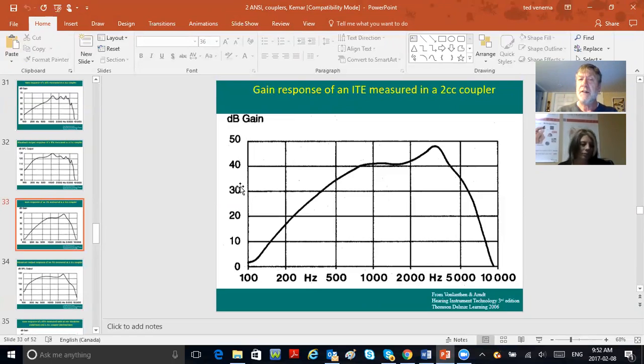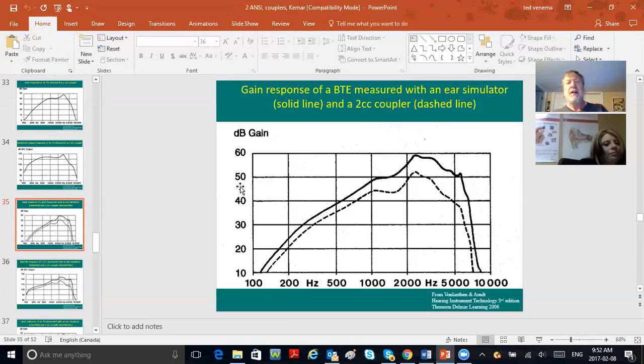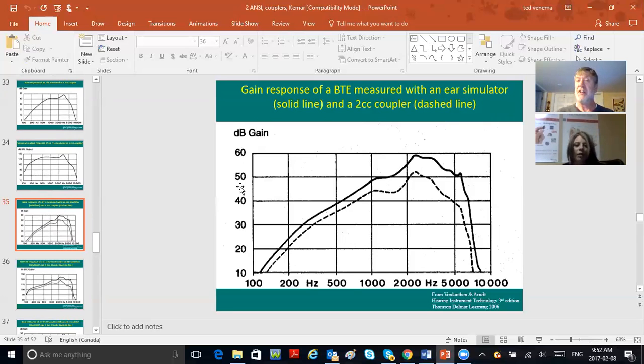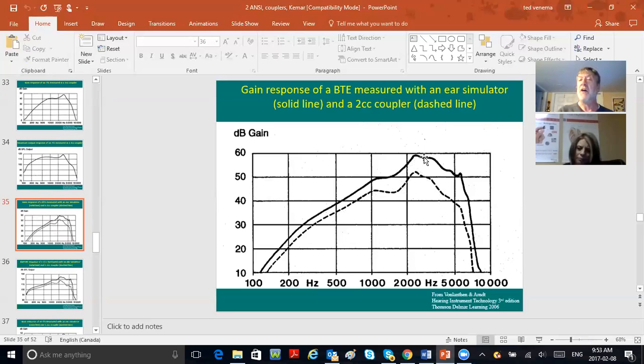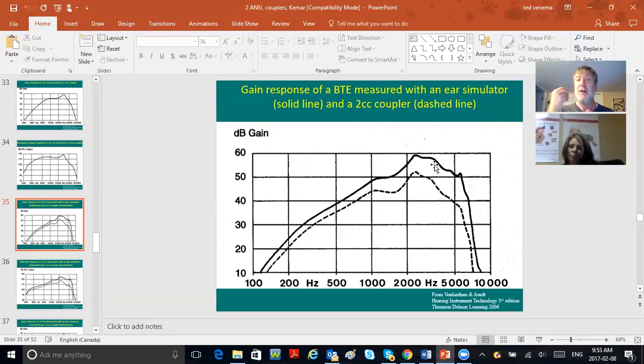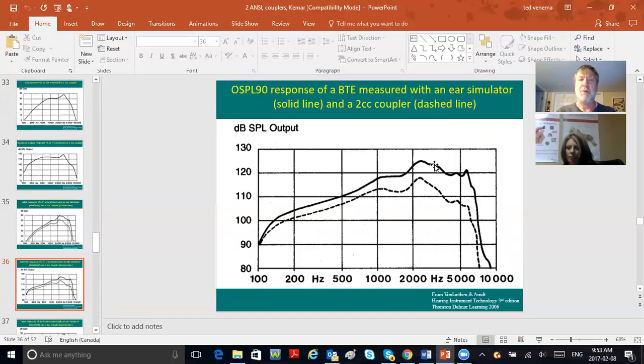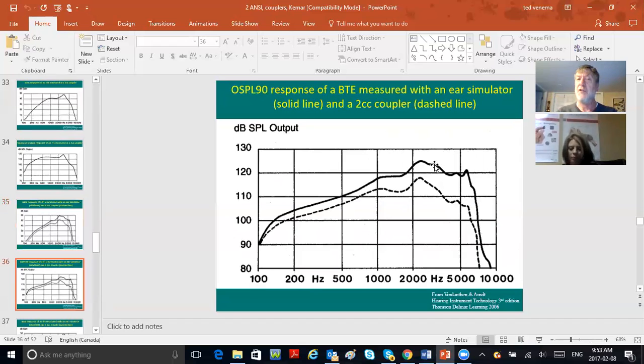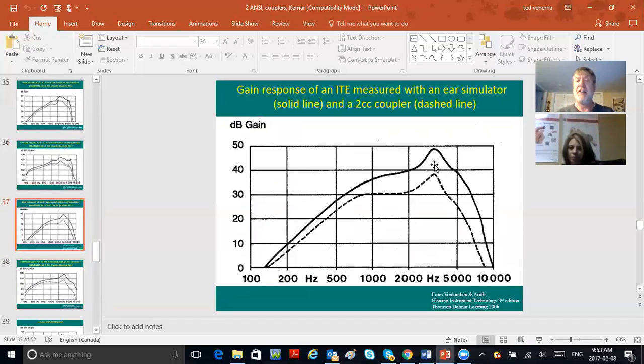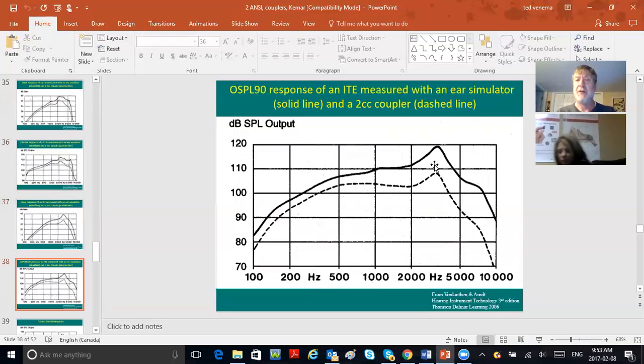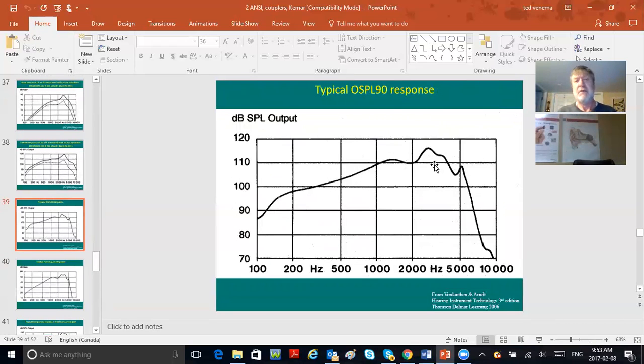Now you're looking at KEMAR and real ear to coupler difference. Here's gain in a BTE in the 2cc coupler shown with a dashed line, and now you're looking at it in KEMAR's ear, which is more like the human ear—about 5 dB in the lows, about 10 dB in the highs. The real ear is always more because the space is smaller. This logic applies regardless of whether you're measuring OSPL 90 or gain.